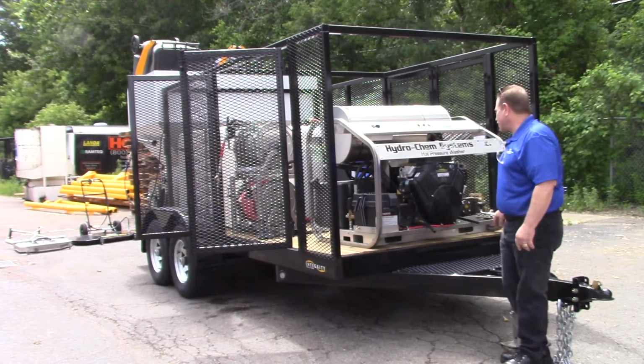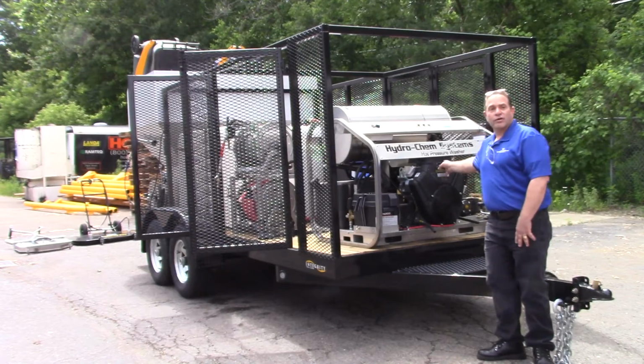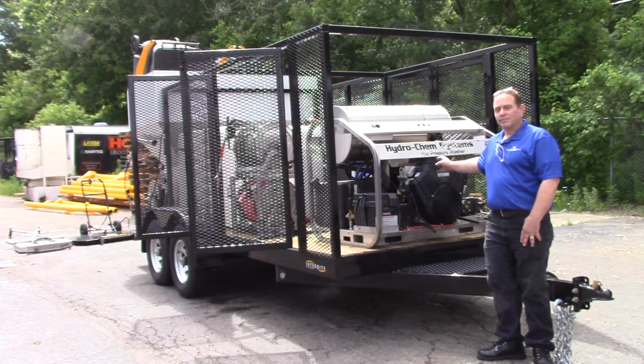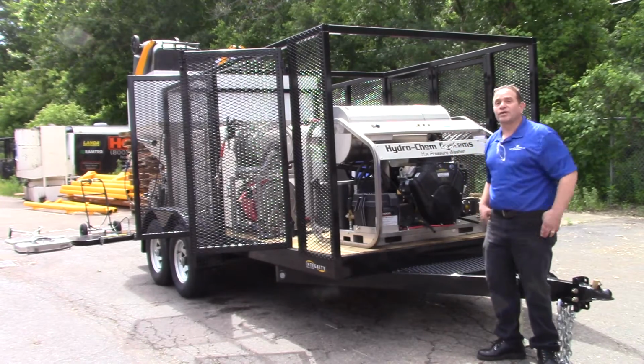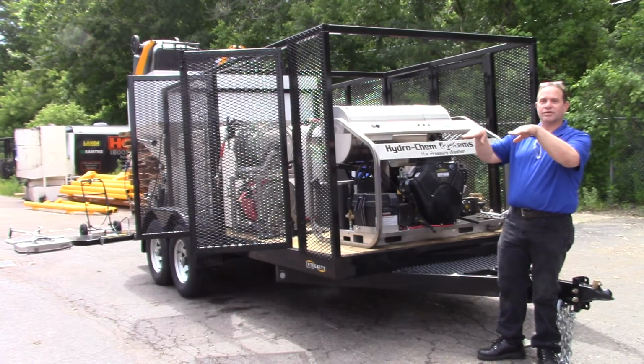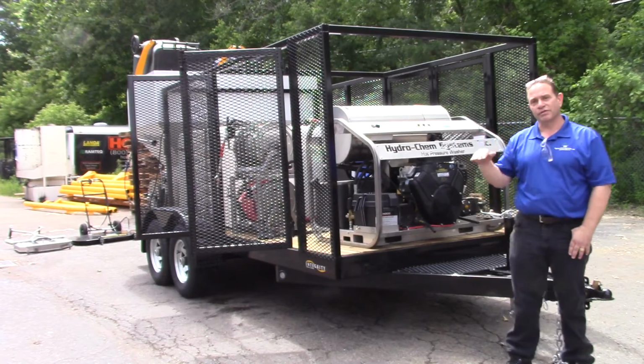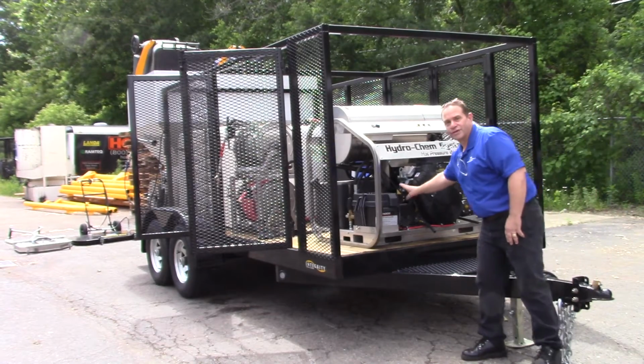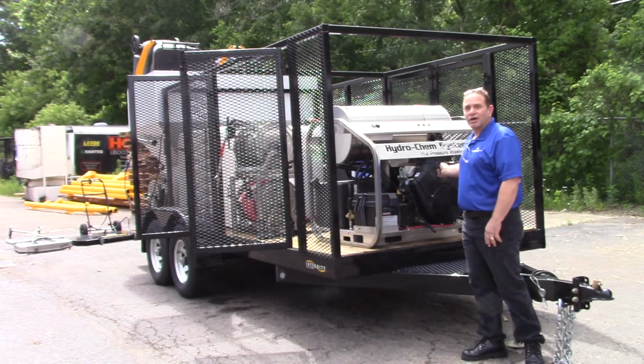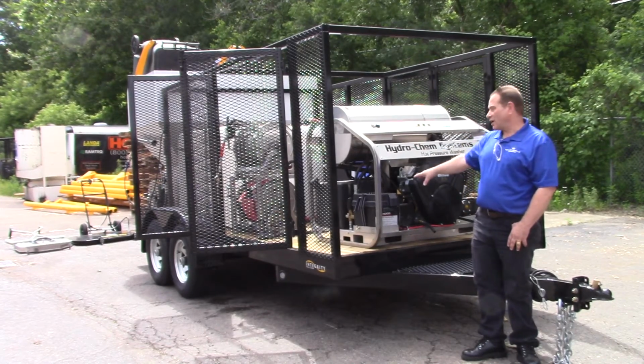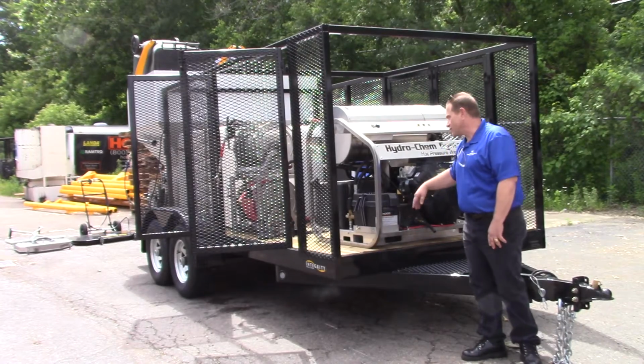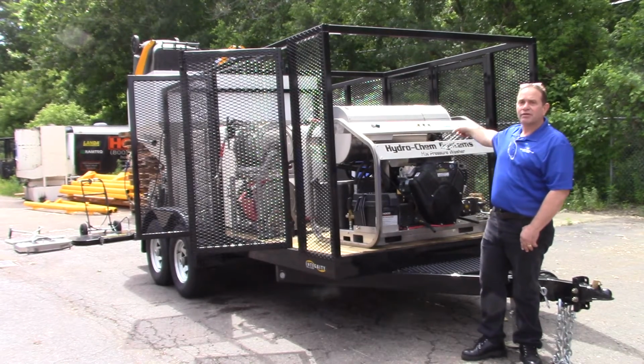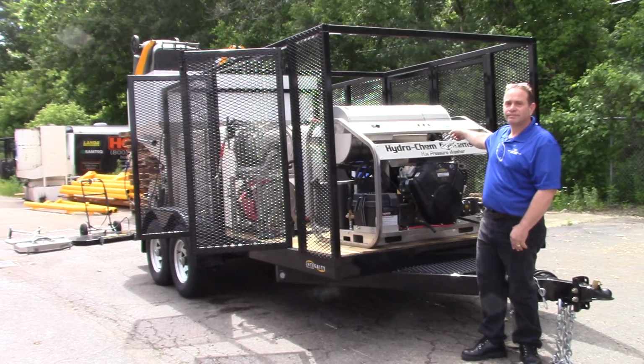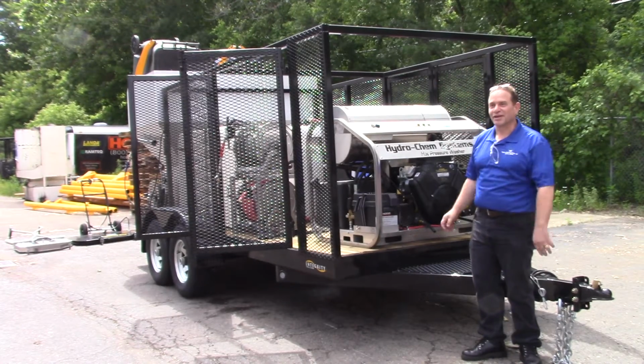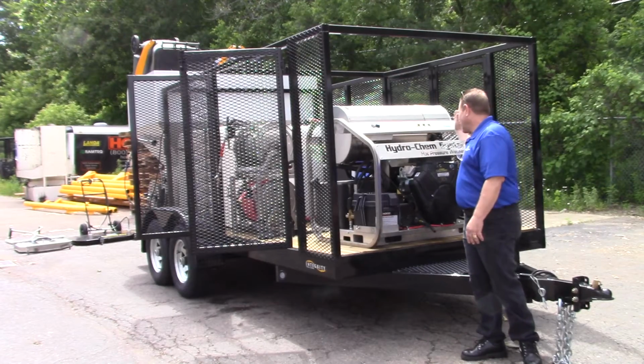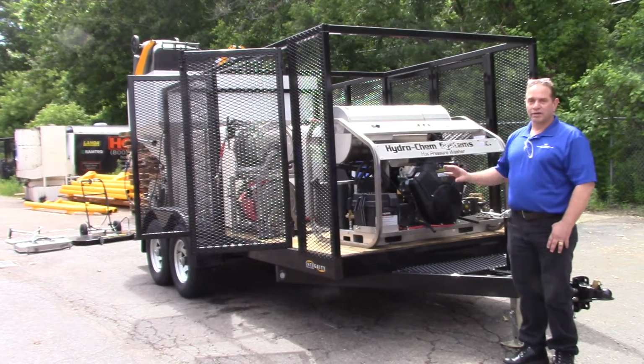The other important aspect on the machine, if you see here, is there is no throttle linkage or throttle. Because you have a generator, to get the proper voltage out of a generator you have to have a fixed speed, normally 3,250 RPMs under a load, which will give you the proper voltage. If they had idle down or throttle down, it would just be a nightmare. It would cause all kinds of problems, not only for the vacuum recovery system, but the Beckett burner on here, the high efficiency 110 volt burner. 110, 115, 120, whatever you want to call it, it's all variable depending on the unit. So basically, that's really what it's powering.